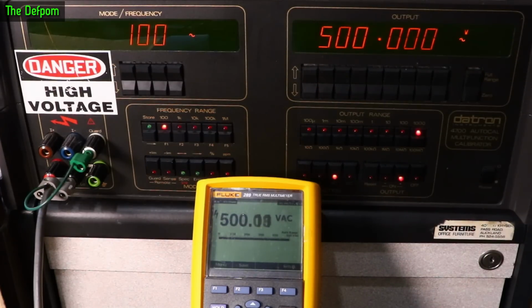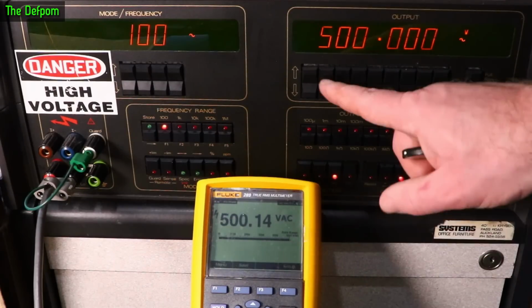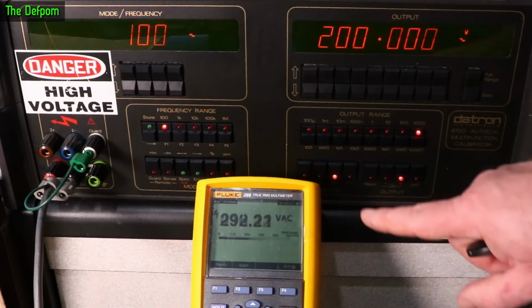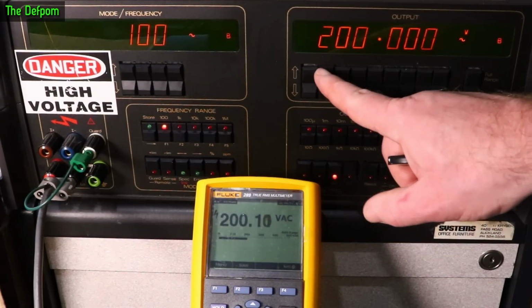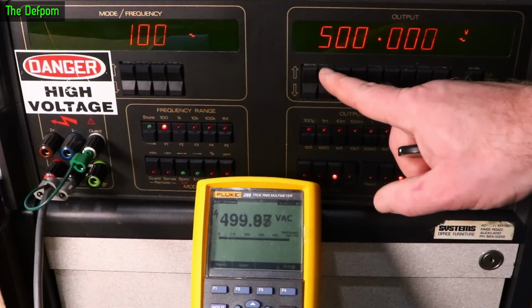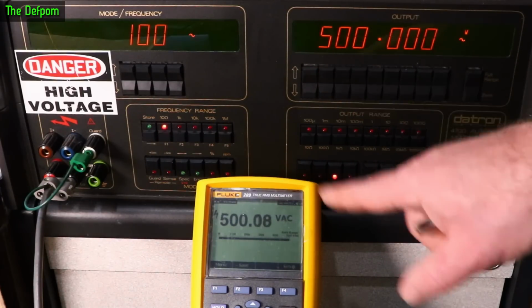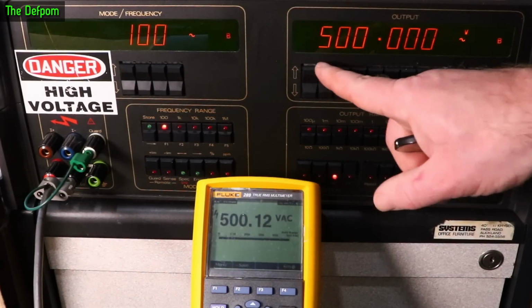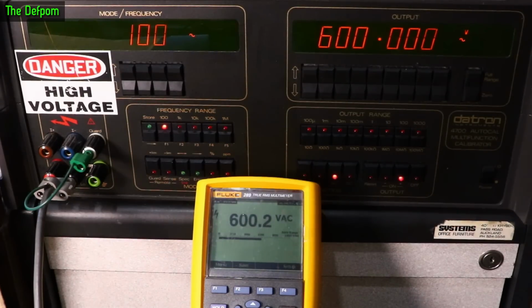500, so that's top of that scale. 14 counts out. Let's just watch the bar graph, see what happens when I change ranges. So it reacts fairly fast. Don't forget some of that delay will be the actual calibrator changing. Alright, 600 volts. Yeah, a couple of counts high. 800 is about 3 counts high. And 1000 is about 3 counts high as well.